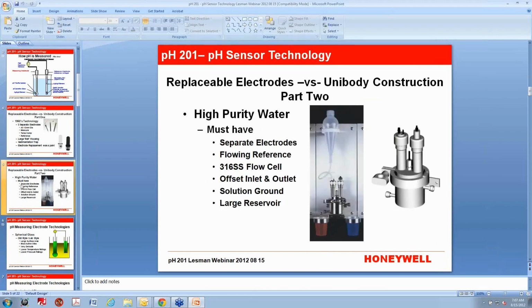Oh, sorry, part 2, I forgot. Part 2 is for high purity water pH. And actually, high purity water requires 3 separate electrodes because high purity water has to have a flowing reference, which means that we're using a liquid potassium chloride. You have a reservoir that holds that potassium chloride with a tube going down into the reference electrode, and then the measuring electrode on the right. You have a temperature sensor in the middle that also acts as a solution ground to take away those streaming voltage potentials which you get in high purity water, because high purity water doesn't have very many ions in it. So you have to have that solution ground.